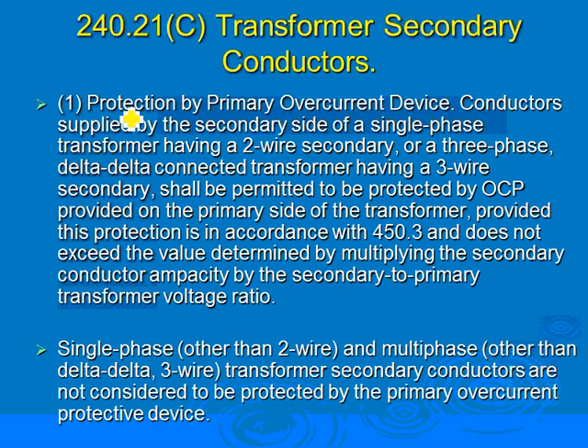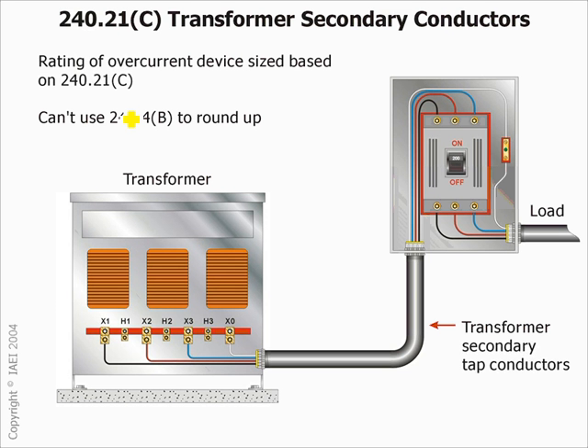Tapping the conductors. And we talked about, guys, tapping conductors. Rounding up, you cannot round up with tap conductors. This is one of the most important things. So here's my question for you. Can this be a 400 amp and this cable is 500 kcmil? Can this circuit breaker be a 400 amp and this conductor be a 500 kcmil? No. Why? Because 500 kcmil can give you 380.